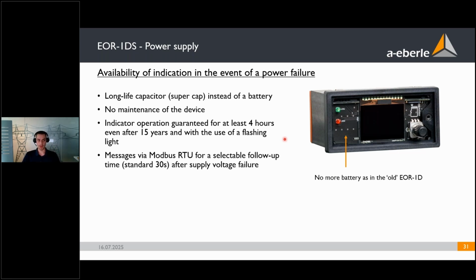The EOR-1DS also grants availability of indication in the event of a power failure, and this is done by a long life capacitor or a supercap instead of a battery. This is done simply because there is no or really reduced maintenance of the device. You don't have to change a capacitor nearly as often as a battery. And this way we guarantee that you have indicator operation for at least 4 hours, even after 15 years of installation, and even when using the blinking lights.